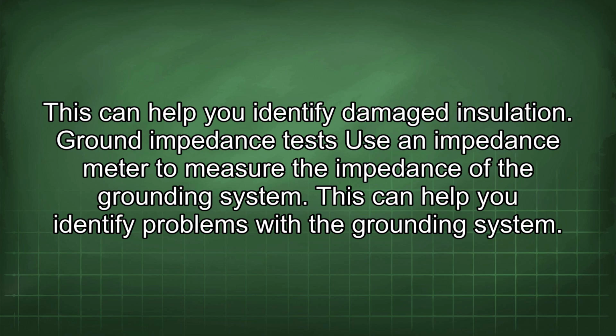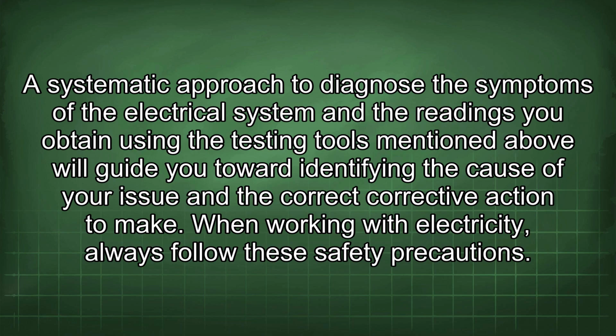Ground impedance tests use an impedance meter to measure the impedance of the grounding system. This can help you identify problems with the grounding system. A systematic approach, knowing the symptoms of the electrical system, and the readings you obtain using the testing tools mentioned above will guide you toward identifying the cause of your issue and the correct corrective action to make.